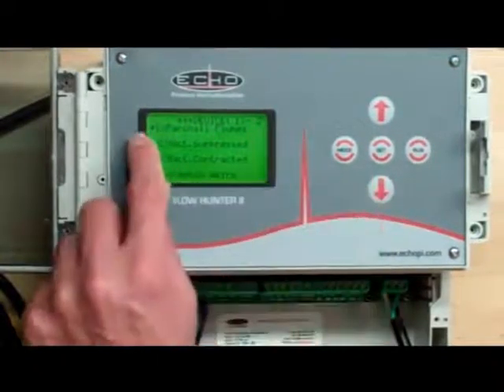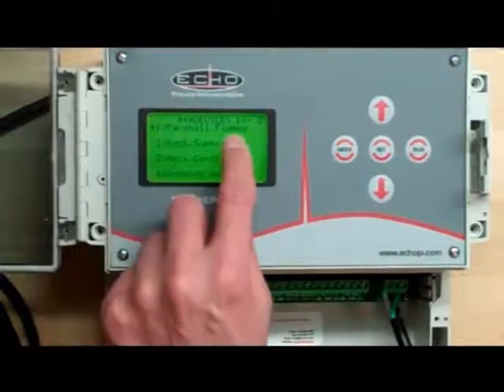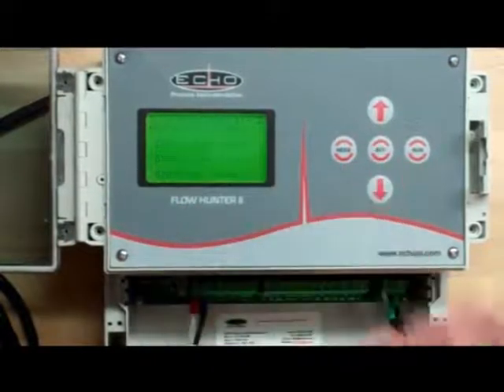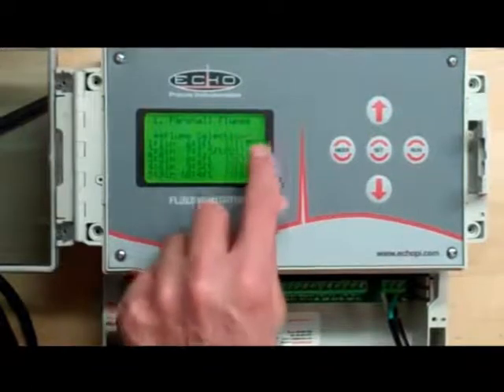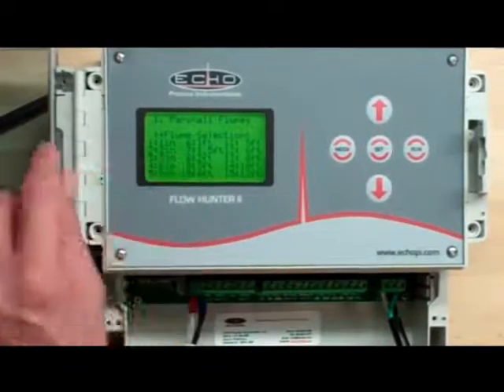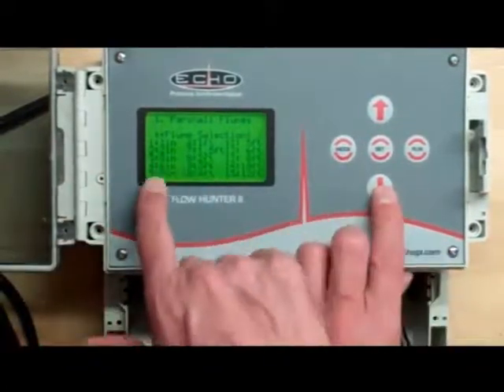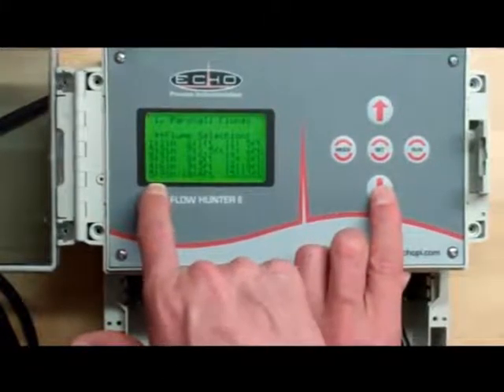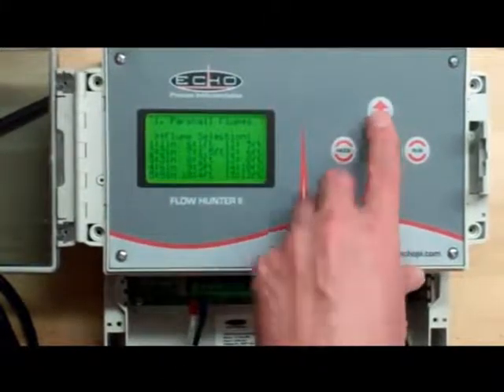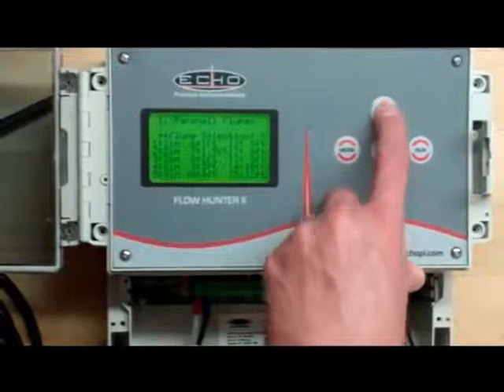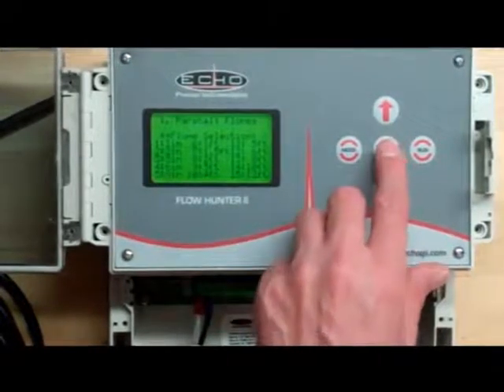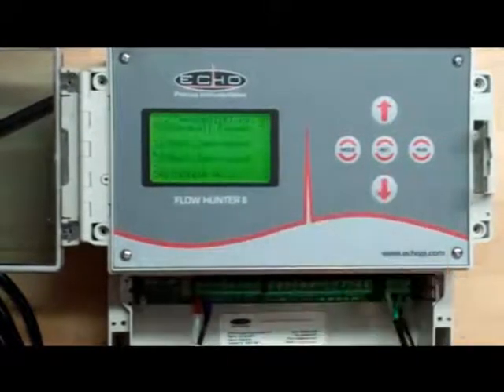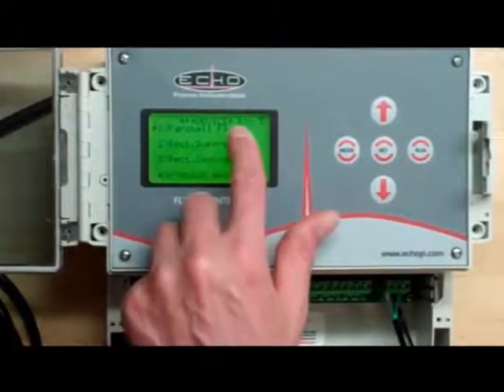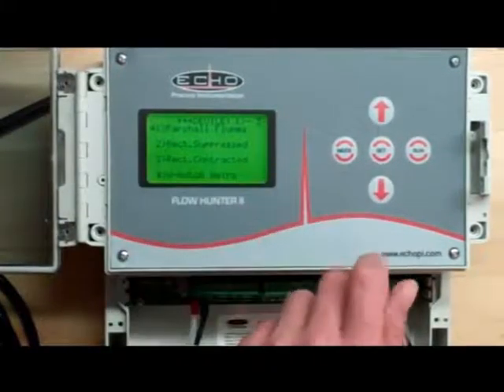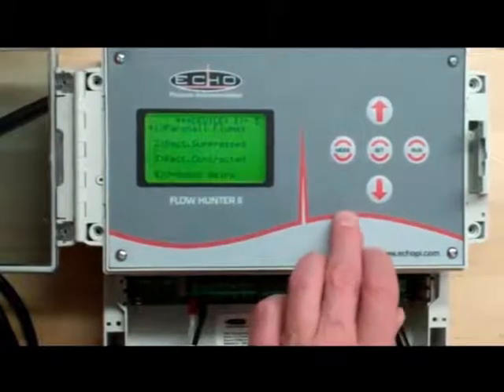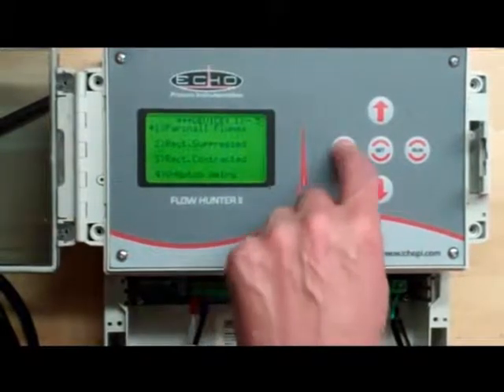So if we go ahead and see the asterisk here at 1 for Parshall flume, we're going to hit set to enter. And then number 2 is what's selected, which is a 2-inch. So let's go ahead and change it to a 9-inch Parshall flume, which is number 5. So we're going to go up to 5. Hit set. Now you see the numbers 1-5. That's Parshall for a 9-inch flume. Now we're going to hit mode to go back to the main menu.